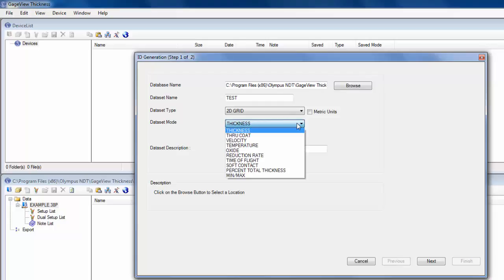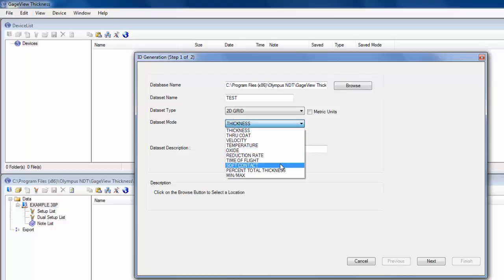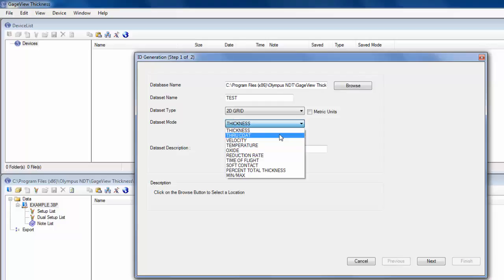So if it's just normal thickness, I would just leave that as thickness. If I'm doing through coat, where the instrument measures a coating thickness and a steel thickness, then I have to specify when I build the file, so the instrument knows to save multiple readings. Likewise for any of these other modes, you just have to specify. Otherwise you get an error message that says, only normal thickness readings allowed in file. So that means that maybe you're doing through coat measurements, but you created the file as thickness, so the instrument won't allow you to save the coating and the steel thickness.